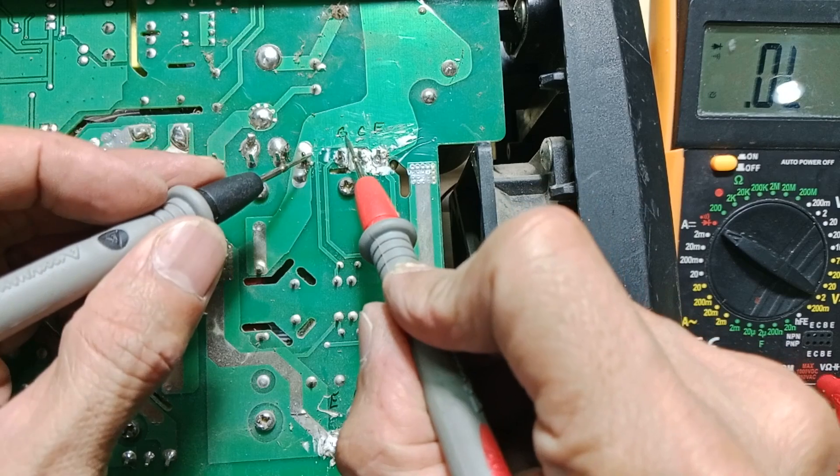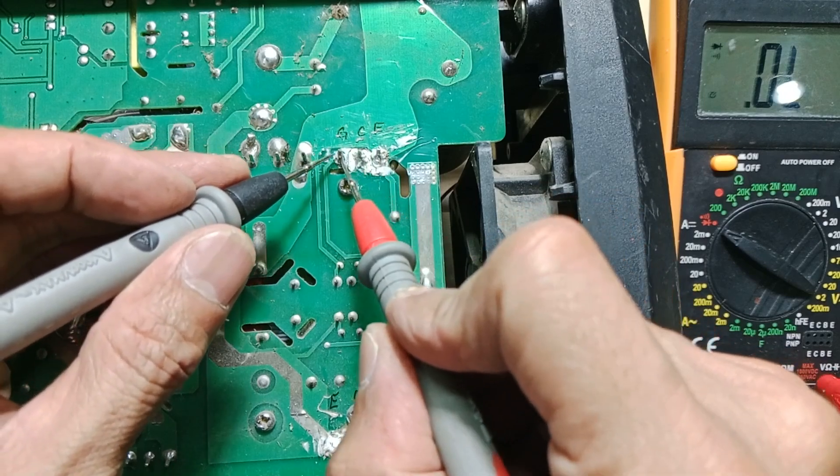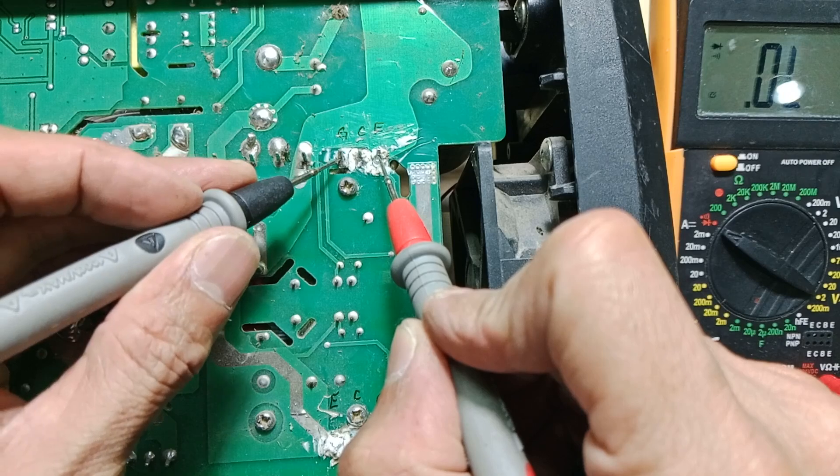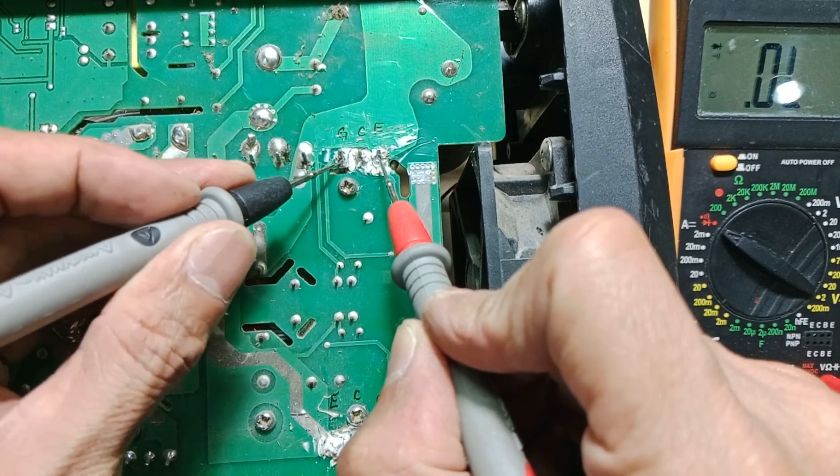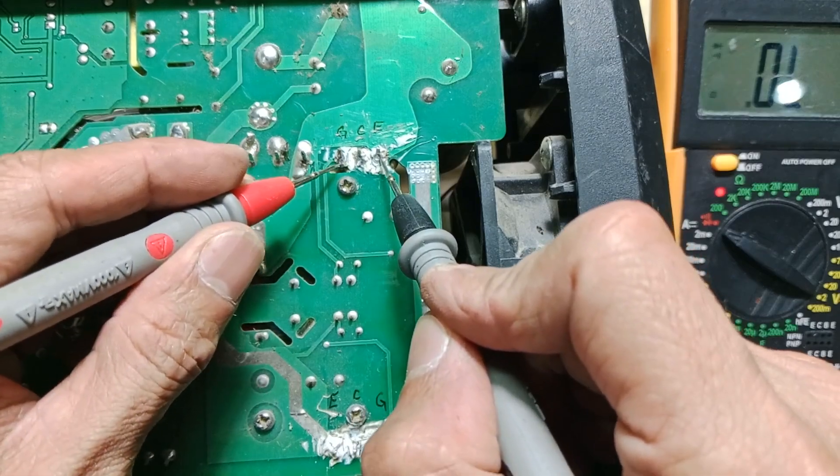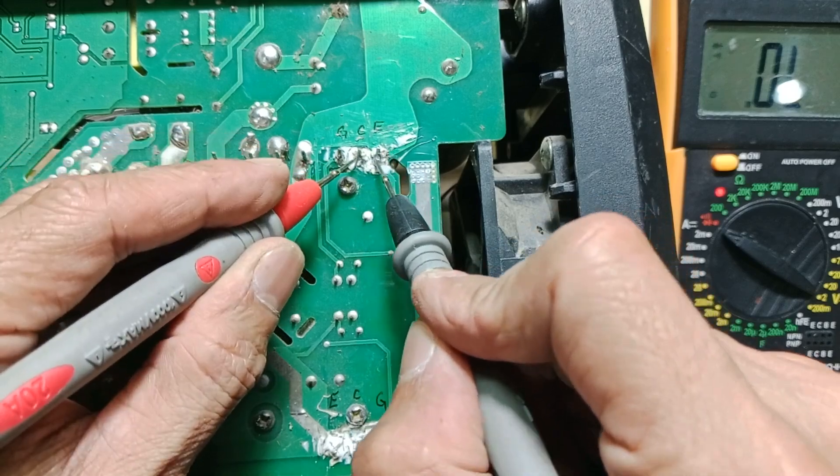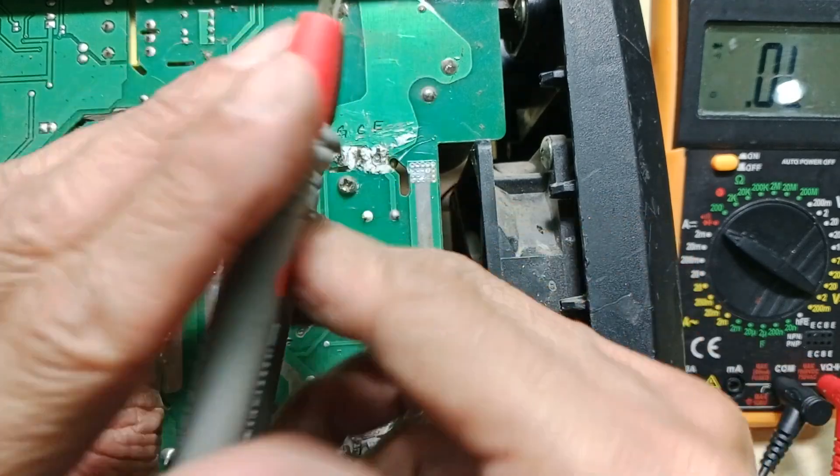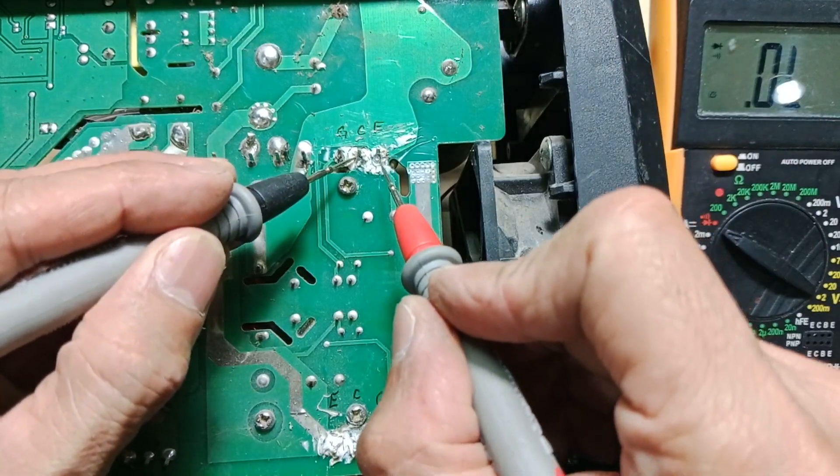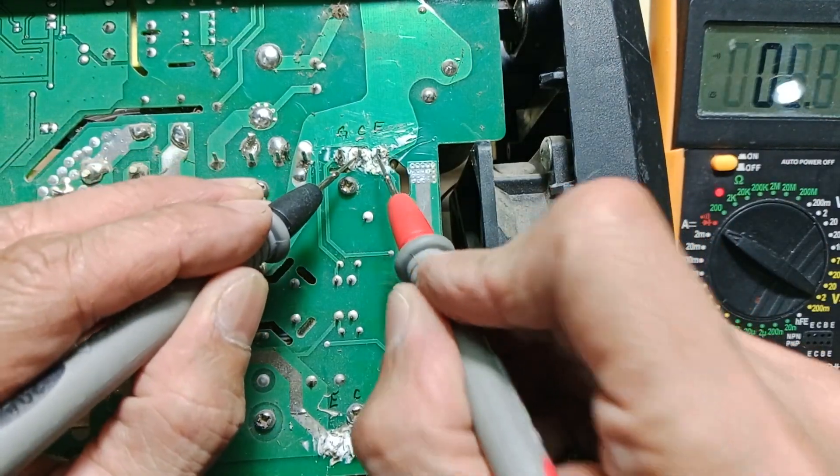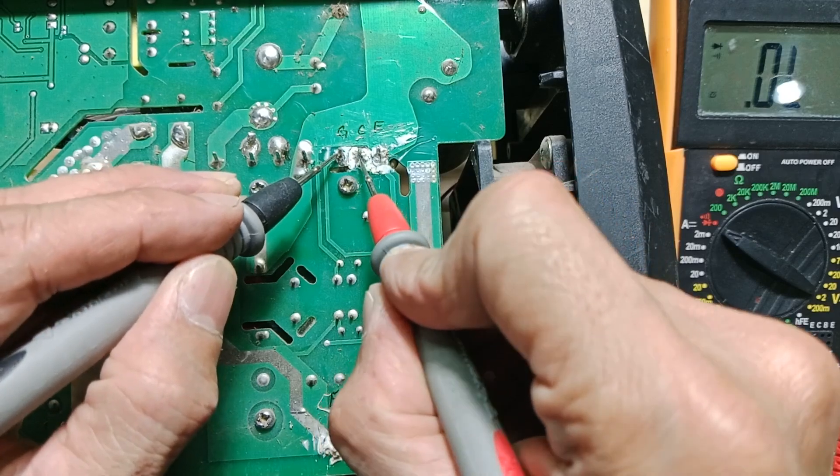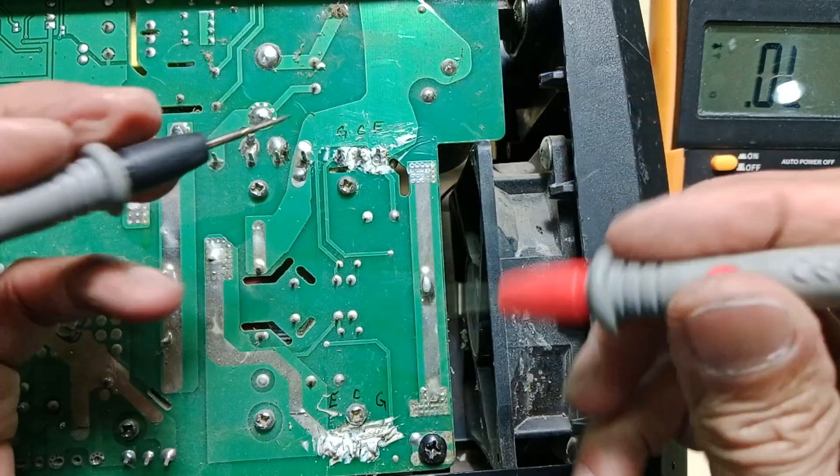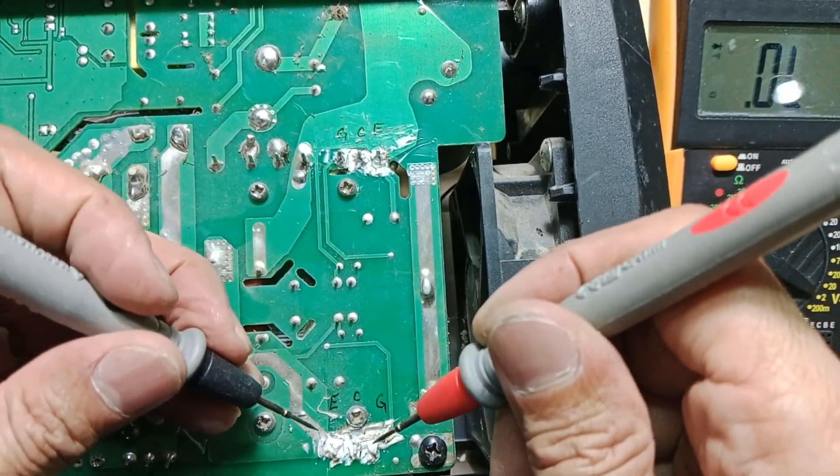I labeled the IGBT terminals on this board so you can easily follow the testing that I will do using the diode check function of the multimeter. I check the collector to emitter junction and they are shorted. Normally we should be getting diode voltage between the collector and the emitter. The gate to collector is also shorted. This IGBT is definitely broken.